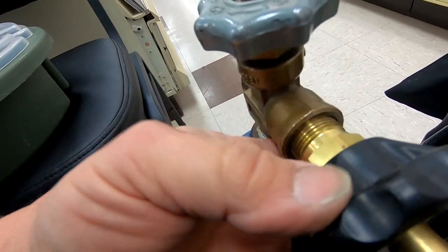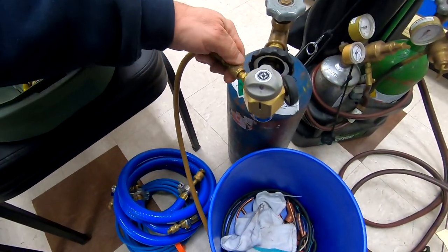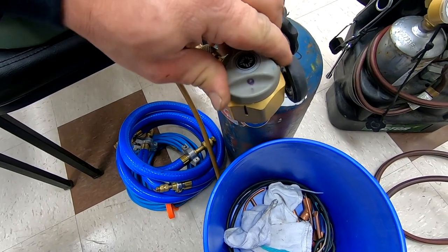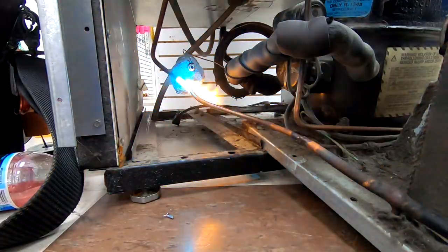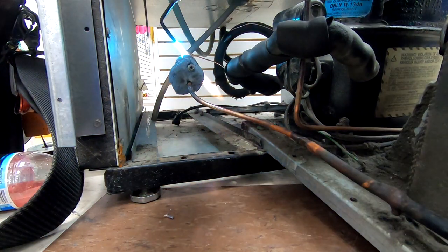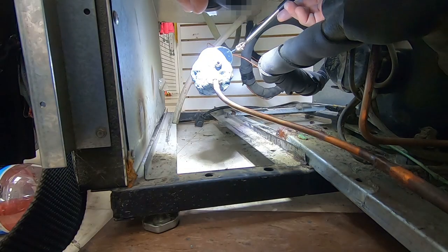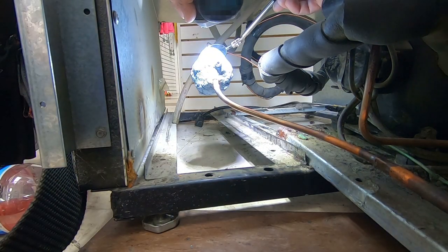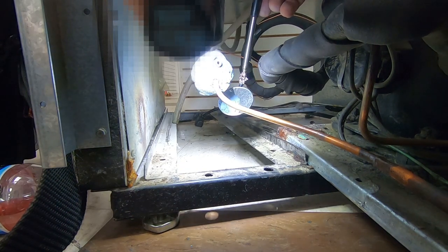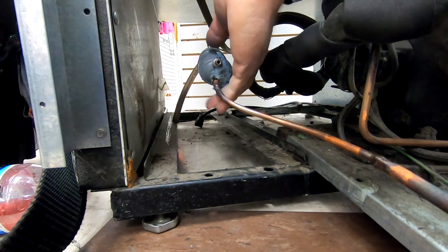Get our nitrogen ready, pull our valve core out — purge the system with any air or leftover refrigerant that might possibly be in the system. Go ahead and get her brazed in. We've got the hot block on the filter dryer, nitrogen is flowing. Inspect the joint, remove the hot block, and we're gonna put that back in the container.